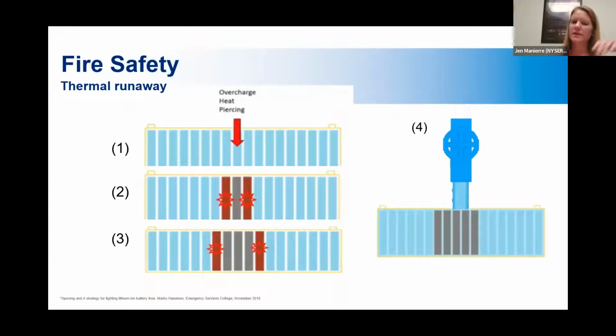And this right here is just sort of an image of that thermal runaway that I was talking about. So you have perhaps a cell that's damaged, it starts overheating, it heats up the two next to it, moving down to the number 2 row there. They start heating up, and so on and so forth. And honestly, one of the best ways to deal with this once it's already happening is water. You've got to cool them off and stop the overheating process.